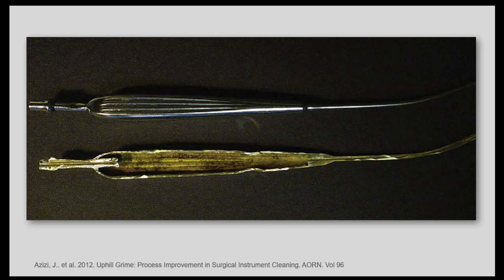And that is why ultrasonic cleaning with lumen flush and this kind of device is absolutely important. So if somebody asks me to audit their unit or do a walk around in the unit, one of the things I do is I say, please give me a swab, and I shove it up, normally the front or the back. But remember, when I'm testing that, I'm only testing this little part over here. I can't get in here to test that section. Often when I do that, firstly, I can often not get the rose tip off because it's so caked on. And then often I'll find a huge amount of debris in the front or the back. If I don't find it, I'm relieved, but it doesn't mean the instrument's actually clean, because inside there, look at the design of that Yankauer sucker. It is complex. And these are the things we really need to think about.